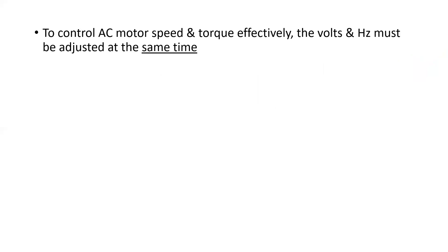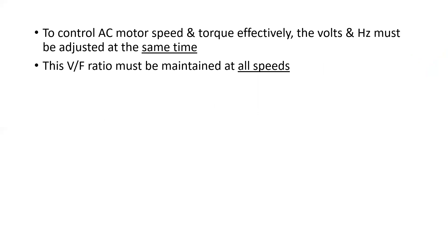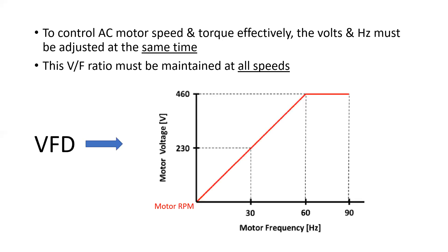To control AC motor speed and torque effectively, the volts and the hertz must be adjusted at the same time. This V/F, or voltage-frequency ratio, must be maintained at all speeds. We see different types of graphs and diagrams that illustrate this relationship — the VFD is adjusting the voltage at exactly the same time that it is adjusting the frequency, giving a very linear line of speed that can be adjusted above or below the motor rating.